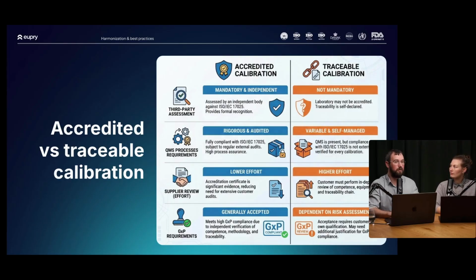That's not the underlying requirement. The requirement is that it needs to be traceable to an international standard, and then you need to assess the competencies of your supplier, and that's often tied to the laboratory actually being accredited. So whilst it's not directly mentioned that it has to be accredited, often we see customers using it as a quick path to ensuring that all of the GxP requirements have been fulfilled. So if you use a traceable calibration option and you actually audit rigorously into your suppliers, that would be okay. That's sufficient, yes, and you would be GxP compliant as well.